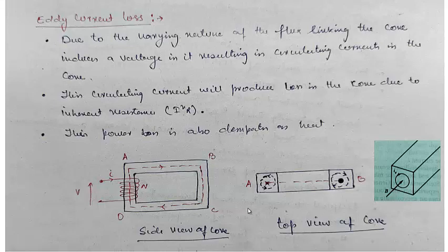In this case, the currents will flow in such a way that they oppose the flux. This circulating current will try to flow so that it opposes the flow of flux, producing flux opposite to that of the actual winding. Since this flux goes from A to D, these eddy currents will try to flow the flux from D to A, so that the net flux is reduced.